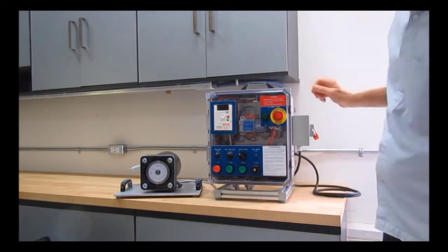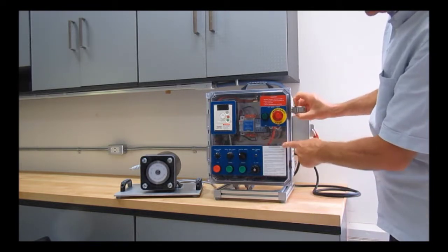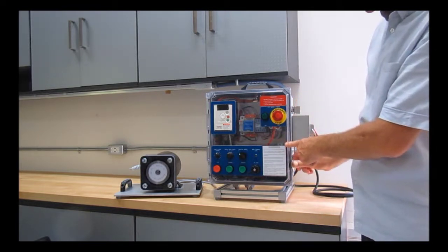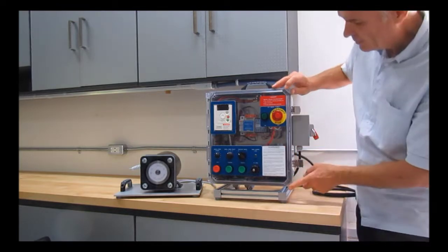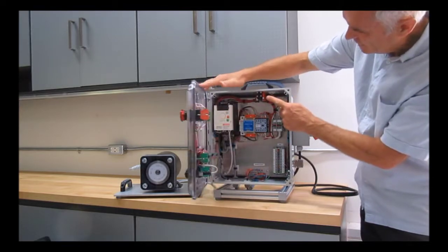I'll quickly open up the enclosure and go over some of the features and talk about some of the operator devices. When I open the enclosure there's a click - that click is a safety-rated limit switch which is interlocked with the master control relay.